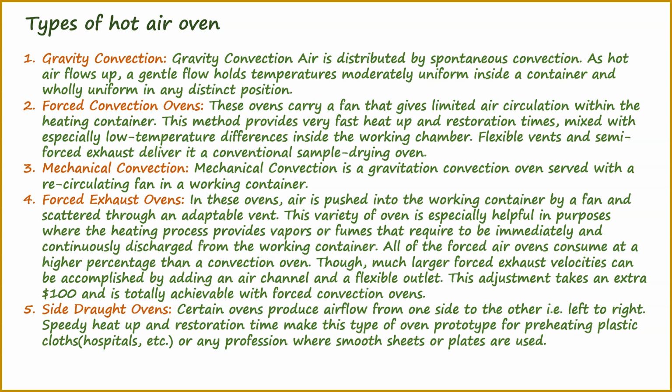Forced convection ovens. The second type of oven is forced convection ovens. These ovens carry a fan that gives limited air circulation within the heating container. This method provides very fast heat up and restoration times, mixed with especially low temperature differences inside the working chamber. Flexible vents and semi-forced exhaust make it a conventional sample drying oven.